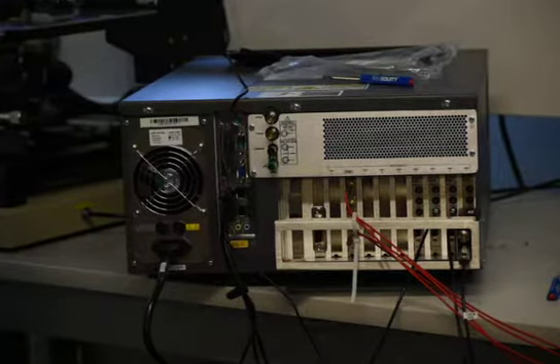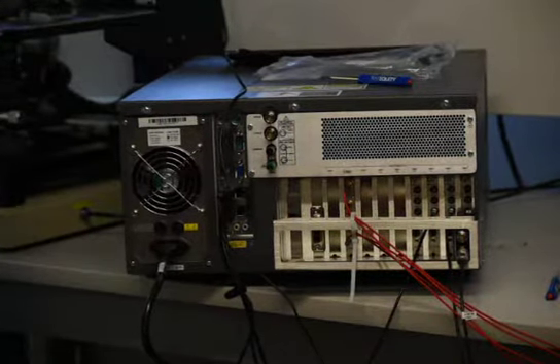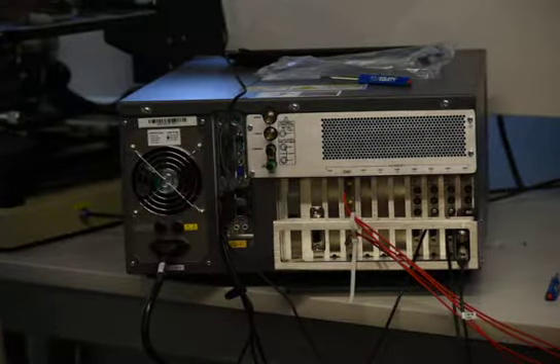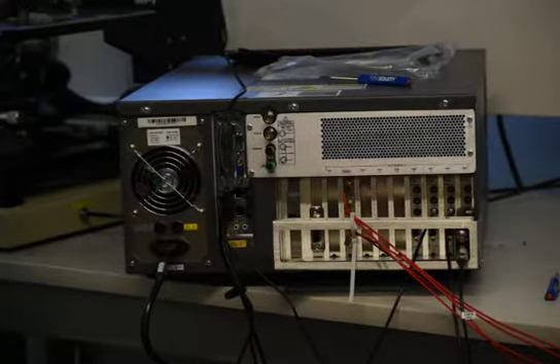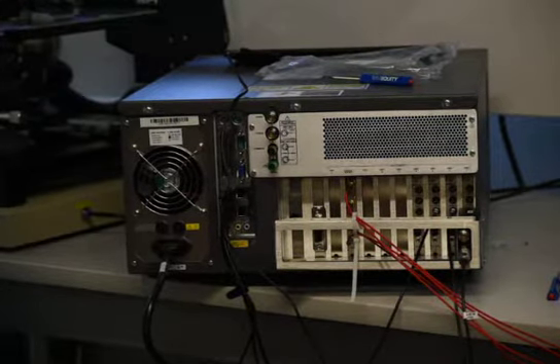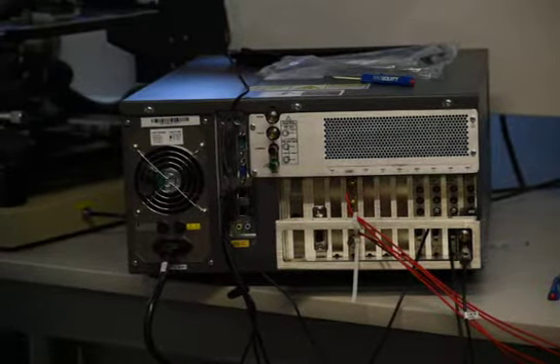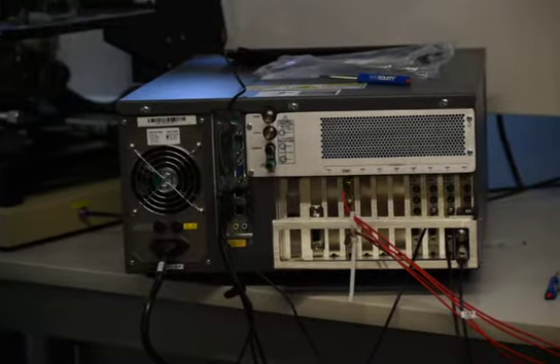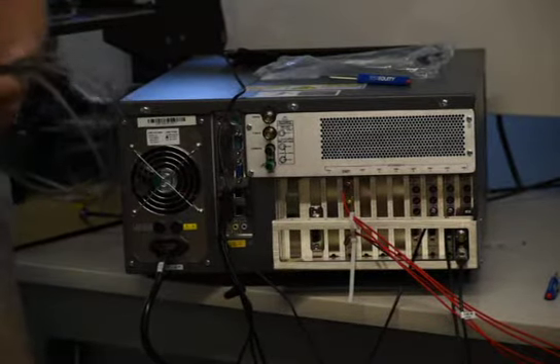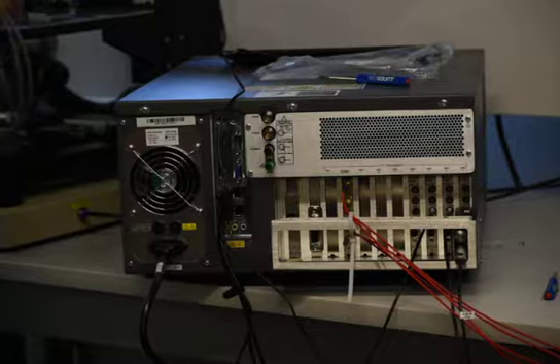So you need some resistance in that probe. They make special probes for that. We sell them if you're interested. We have them, but you don't want to just use a ground wire. It's called a discharge probe. It's got a big handle that's insulated. It's got a shield around it, so you can't accidentally get nailed by it.